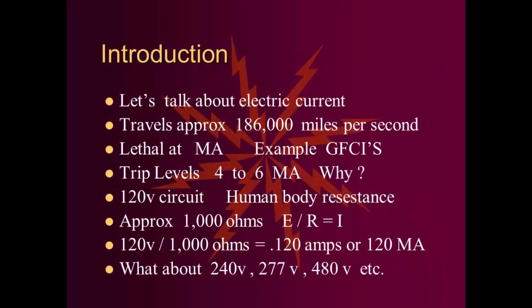Let's talk about electric current for just a moment. All of this is going to help you to appreciate these standards a little bit more. Did you realize that electrons travel at approximately 186,000 miles per second? That's pretty fast. It can be lethal in milliamps. That is thousandths of an amp. Examples, GFCIs, that's ground fault circuit interrupters for personnel. The trip levels for GFCI receptacles and breakers are between 4 to 6 thousandths of an amp.